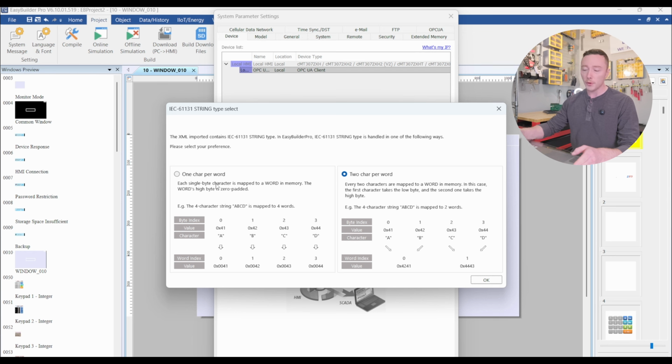Most tag-based PLCs use Unicode encoding format, or basically one character per every 16 bits of data. Some PLCs, as an example a PLC that supports Modbus, will use 1 byte per character. So you want to double check your character requirements beforehand. Usually not a very big issue.